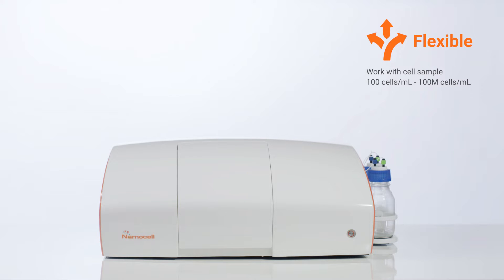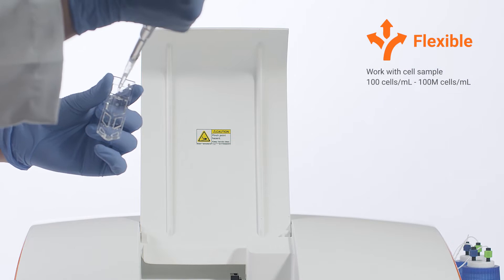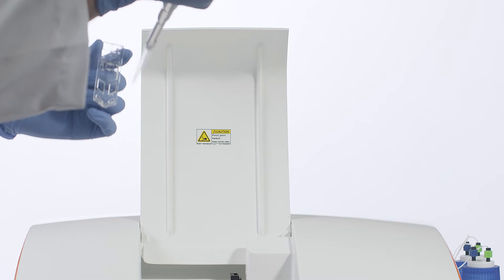Depending on the application, input cell density can range from 100 cells to 100 million cells per milliliter, and either aqueous or non-aqueous sheath liquid can be used, giving you more flexibility.